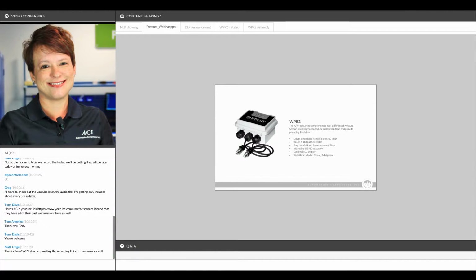There are two versions available. They're both range and output selectable. There's a 100 psi version for your smaller differential pressures and a 300 psi version for your higher differential pressures. Output choices include 0 to 5 volts, 0 to 10 volts, and 4 to 20 milliamps. And you can see by the image on your screen that this is a remote sensor style design, which is really meant to save you time and money in the installation process because you've got two independent pressure transducers on leads that go back to your NEMA 4X housing.